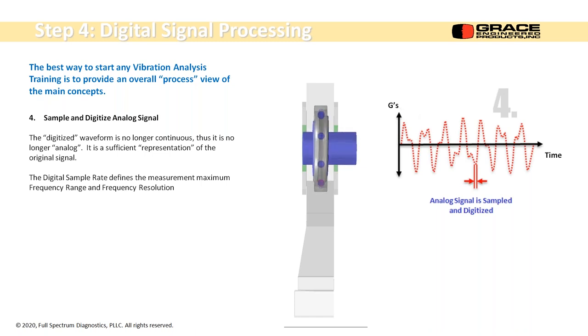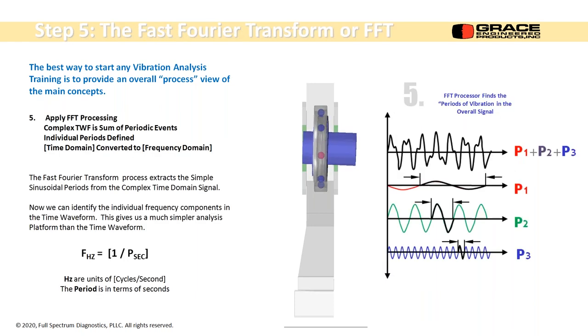So what we do before we pull it into our data acquisition system is we have to digitize it. So we sample it, we digitize it at a really high rate, so that if looking at this, it is a bunch of dots, but you wouldn't be able to see it because there's so many dots and they're so close together. But this is the way the computer can understand it. Okay, so we'll put in that millivolts per G number, we'll pull it into our data collector, we'll sample it and digitize it, and then it's ready for the real analysis, which is the fast Fourier transform.